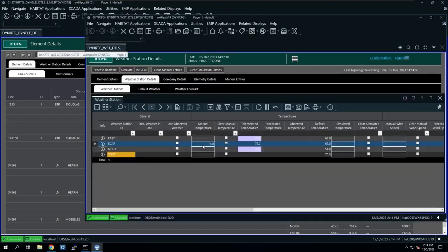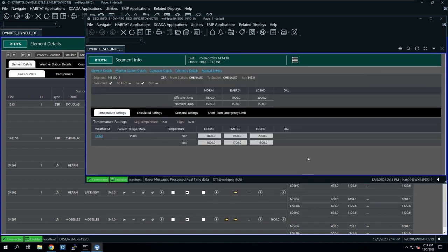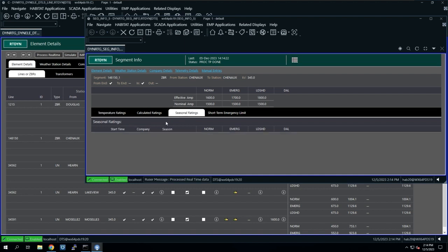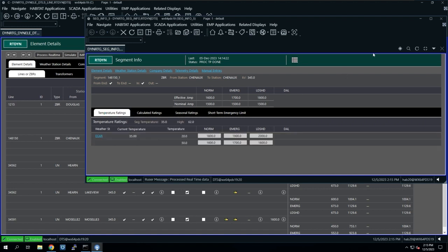If I come in, I can manually change that value to show how the application works. So if we were at, say, 35 degrees, then the application is going to move up to the next most limiting rating set. So it's going to pull the 50-degree temperature set, and it's going to start using the 1600, 1700, and 1800 ratings. You can see that that's currently the effective rating set being used for normal, emergency, and load shed. If, say, my temperature sensor were to fail, if I had bad telemetry on my current temperature value, the application falls back to the next lowest priority with good data quality. So we would fall back to our seasonal rating set, or we would fall back to our nominal rating set.